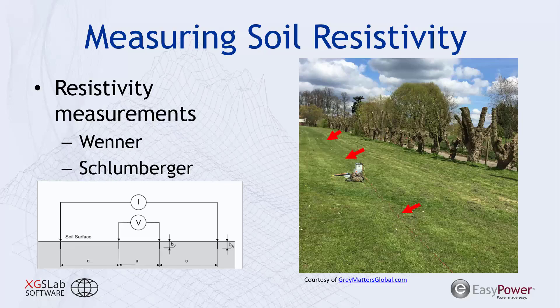Typically, when doing a grounding system analysis, a technician or engineer is sent to the field where the grounding system will be installed. The most common method for measuring soil resistivity is the Wenner method. A test device injects a known current on outer probes inserted into the soil, and voltage is measured on inner probes. As we expand the distance between probes, we evaluate deeper soil layers and understand the electrical characteristics of the soil.